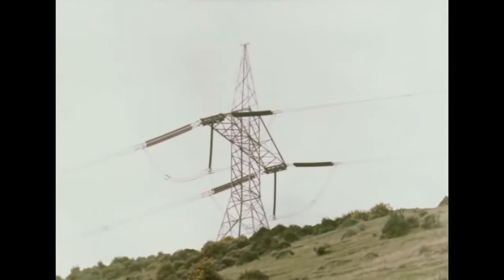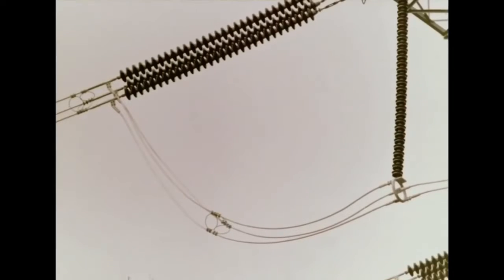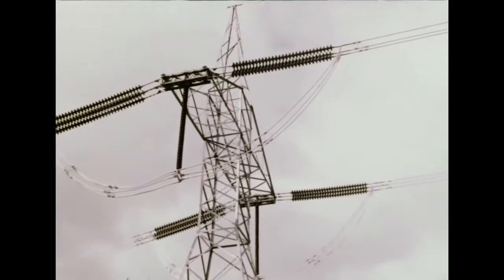Making the conductor of a parallel pair of cables reduces corona loss, but this can be reduced still further by using 3 cables equilaterally spaced. This pattern is used on those parts of the line that come within 2 miles of long-distance radio telephone aerials. Where the line comes within 1.25 miles of the receiving stations, the 3 cables are increased to 4.